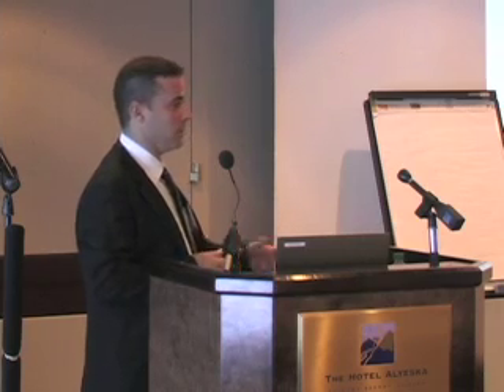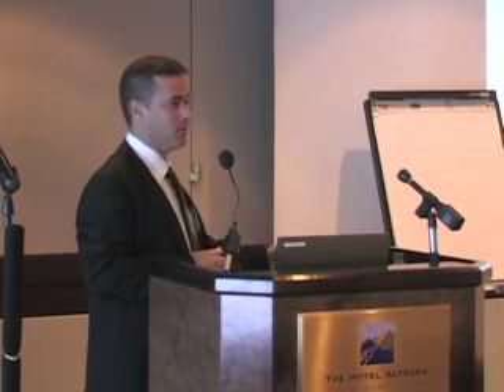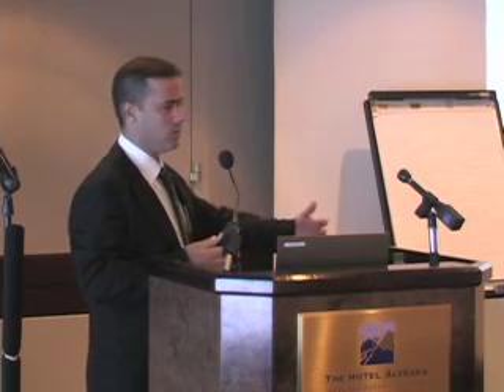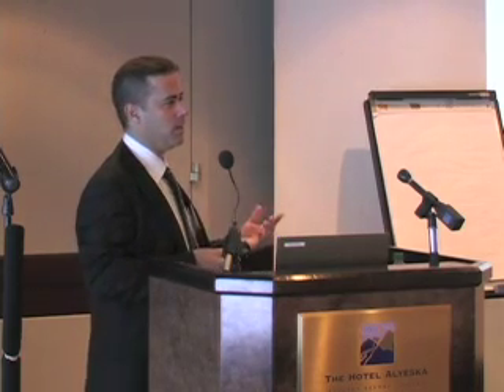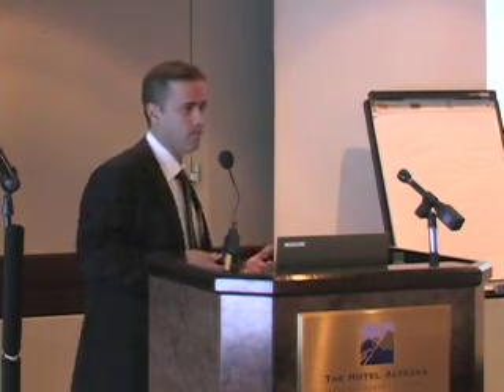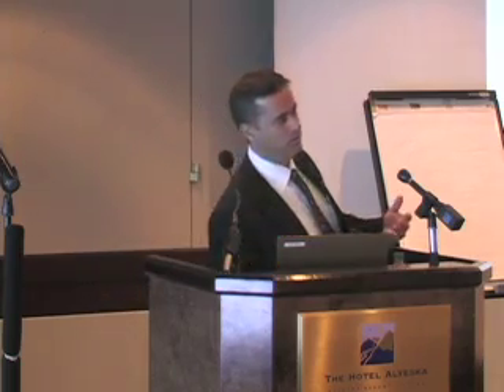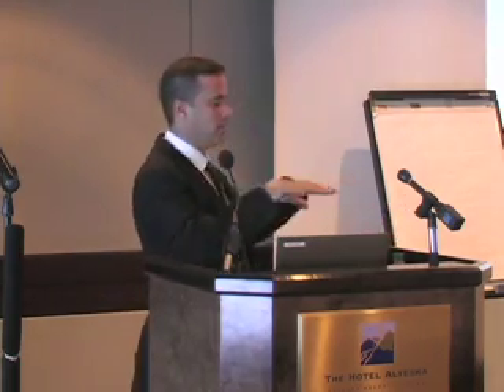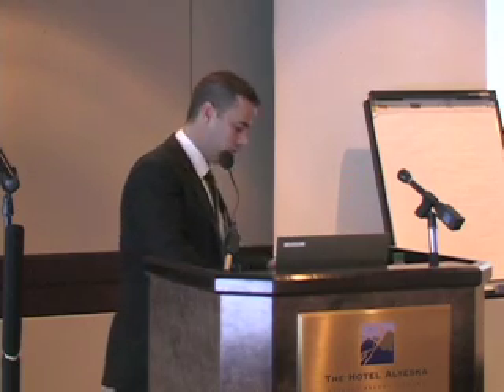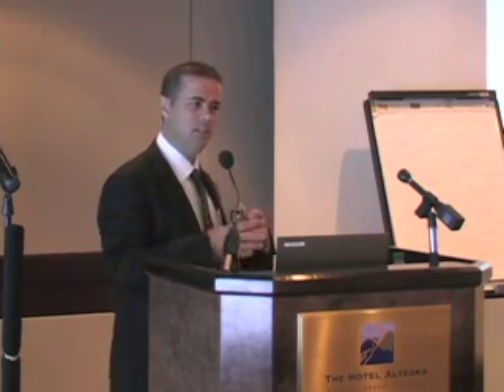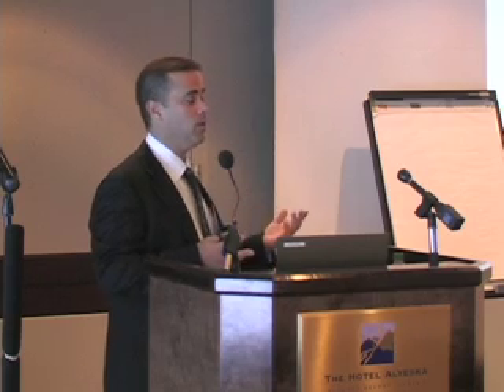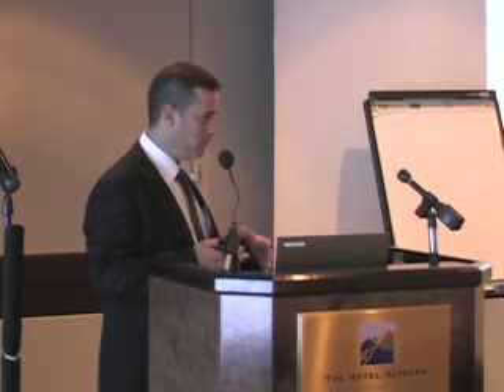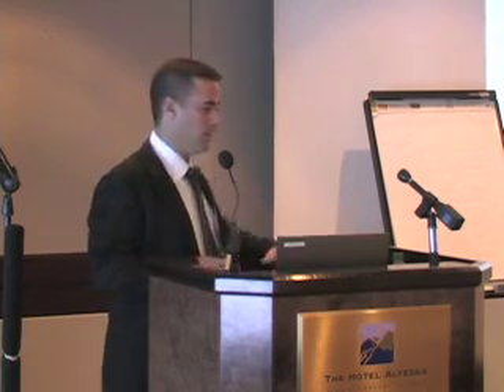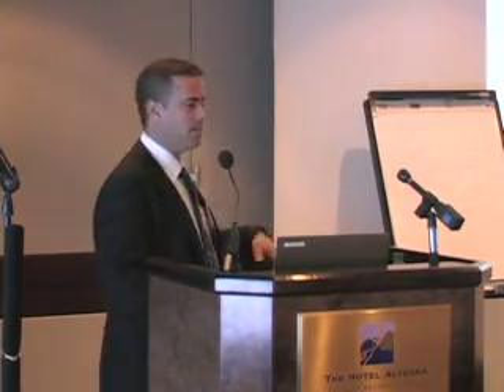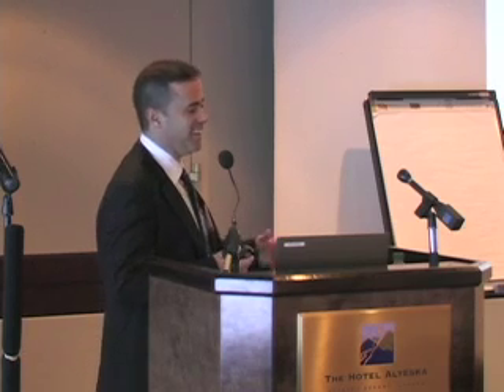So we went and had a look, and sure enough, it was evil. You couldn't get near it because you were getting electric shocks walking towards it. So you're probably starting to understand where I'm going with this. The step voltage between your 2 feet: as a child, your feet only take small steps, and the step potential between your 2 feet wasn't so great, so the kids could walk past this pole. Luckily, no one had ever touched the pole, but the adults taking larger steps were feeling a sensation, or not.